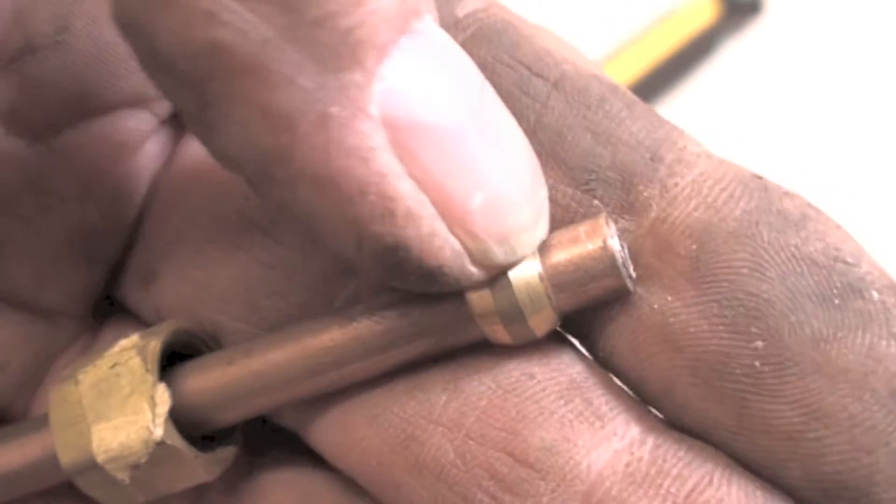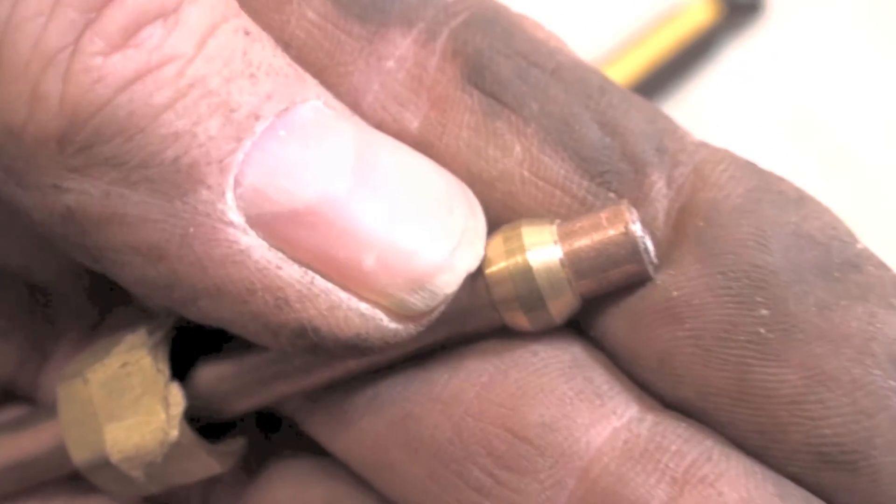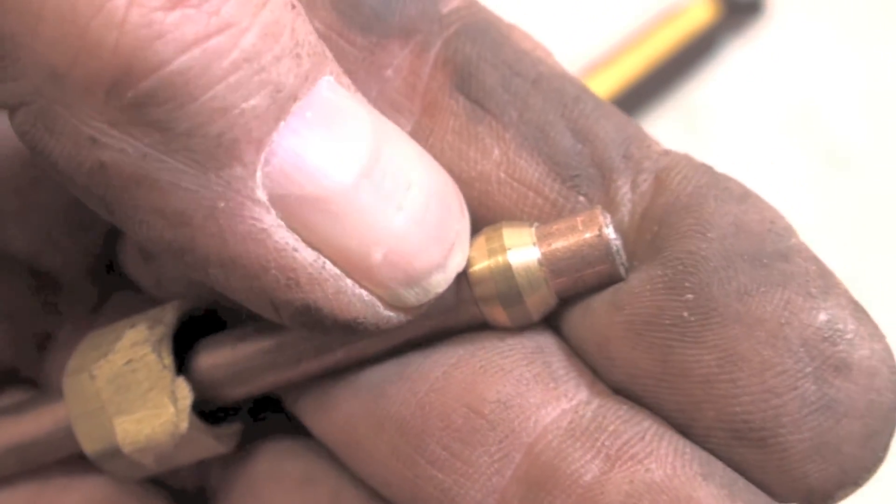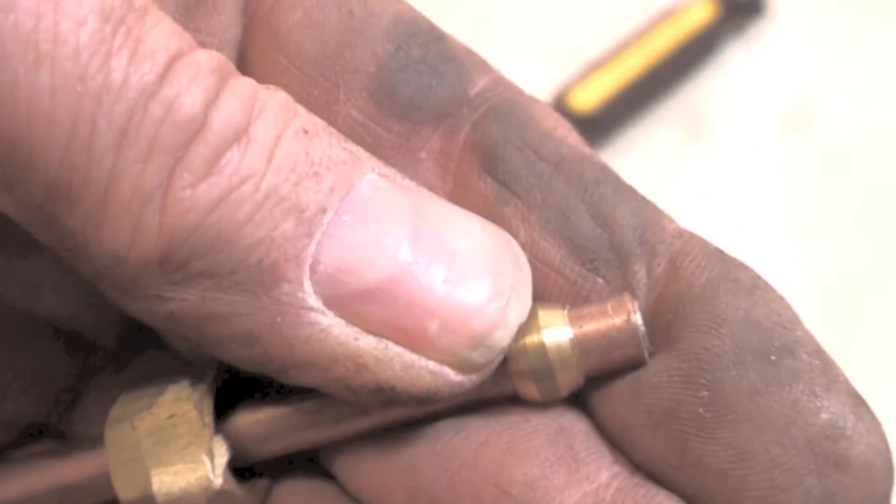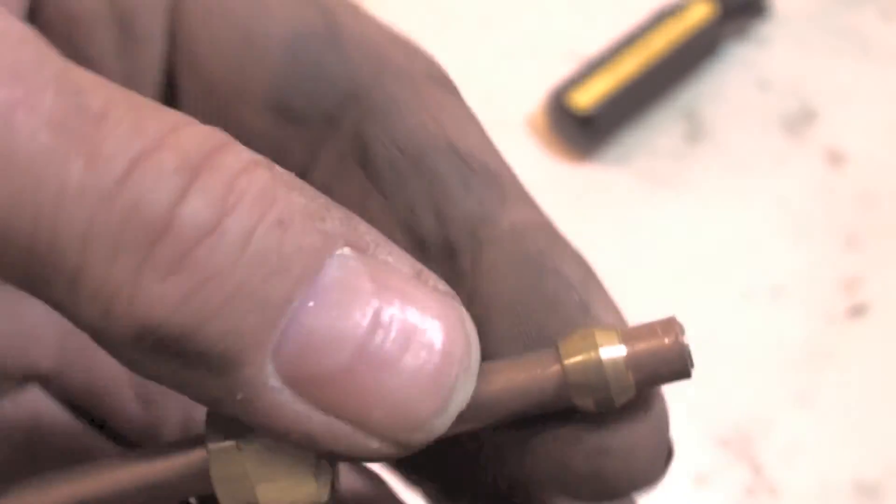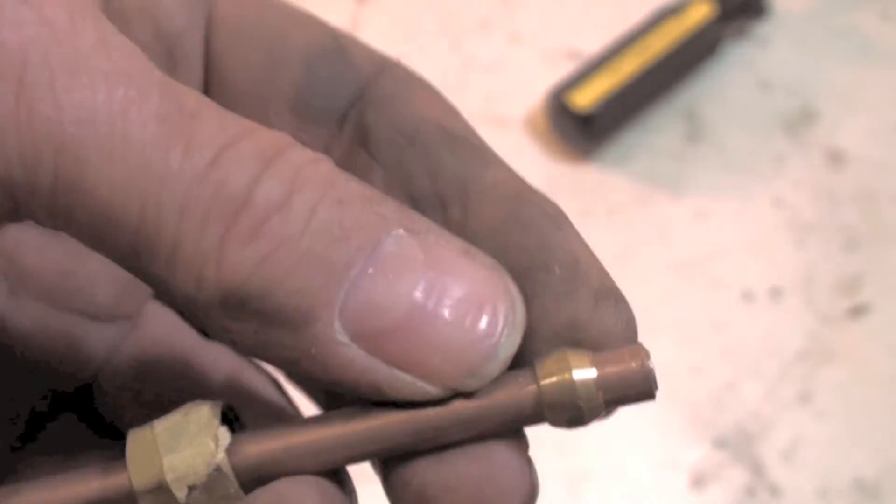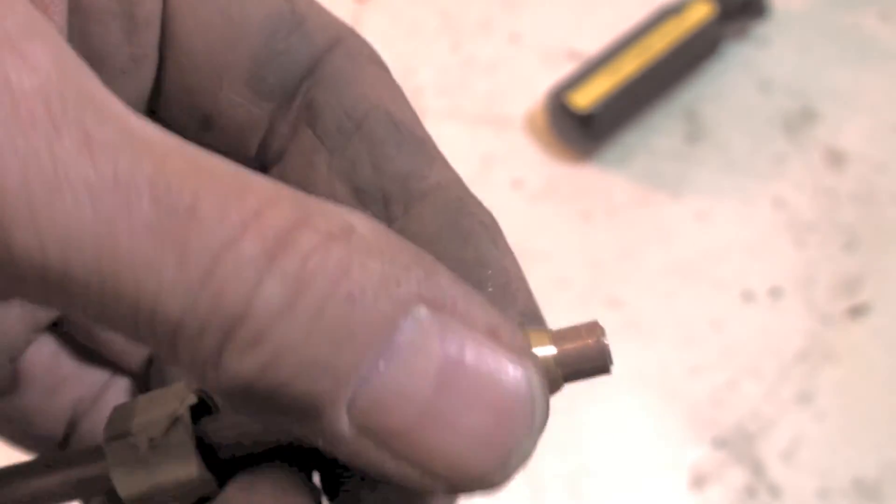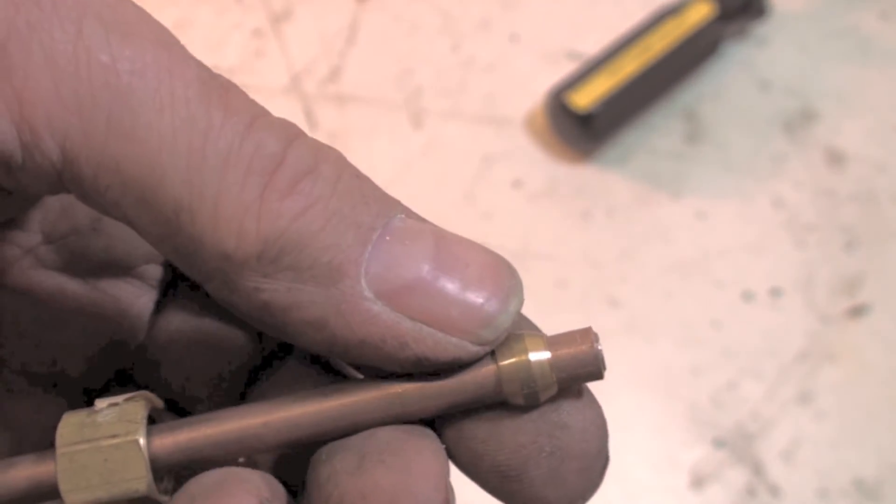You can see it's been squished down right there, and that should seal pretty good. If you have trouble getting this thing to seal, especially with natural gas, a little bit of pipe dope on this thing will not hurt anything. Don't get any on the tubing, but a little bit of pipe dope will seal it.